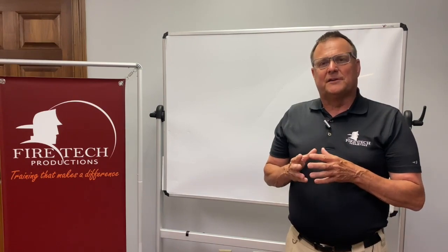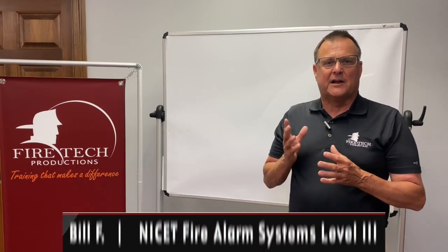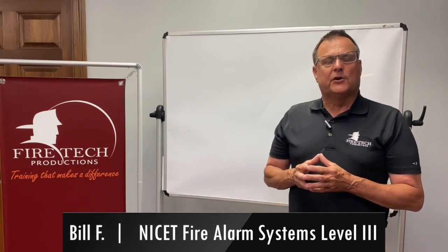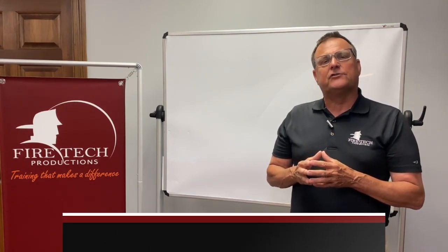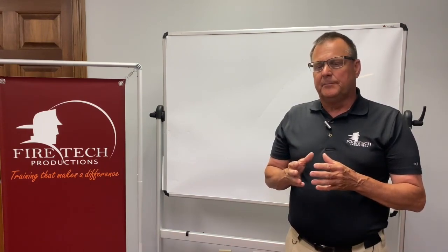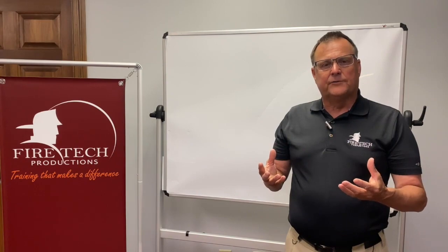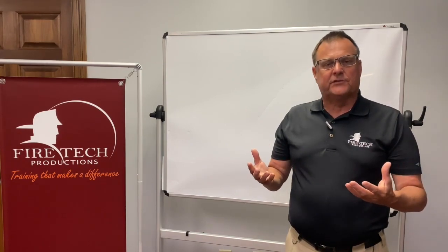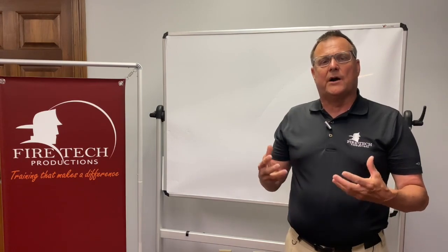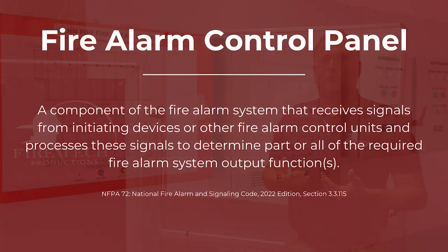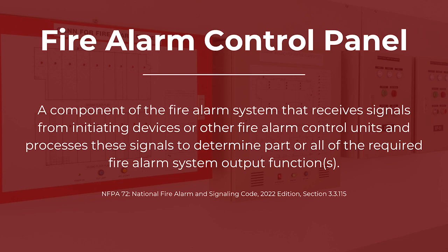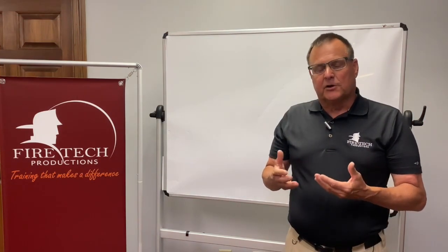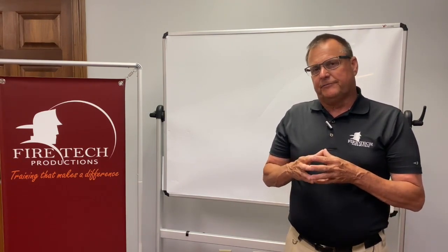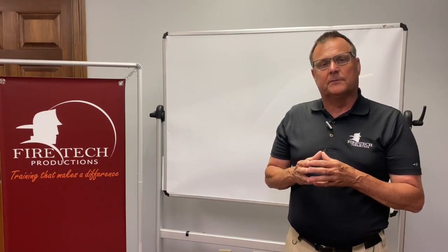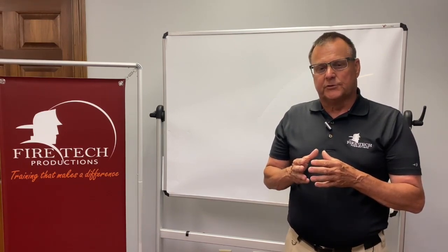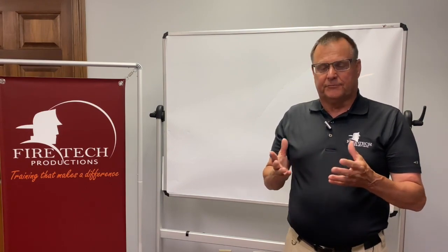When we're talking about fire alarm and detection systems, the control panel itself I kind of refer to as the brain of the system. Because what differentiates a fire alarm and detection system from other electrical systems is the ability to supervise, around the clock, 24 hours a day, 365 days a year, the status of the electrical wiring and the devices attached to it. So the control panel is always going out and processing the integrity of the system, and that term is supervision. That is really the core to making sure that a life safety system is ready at all times to alert building occupants or the fire department if there should be a need.